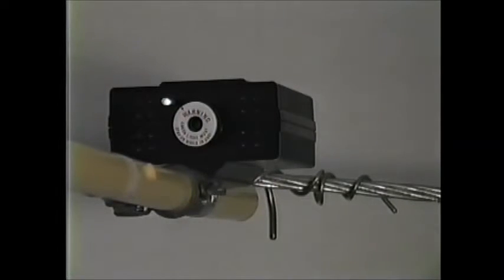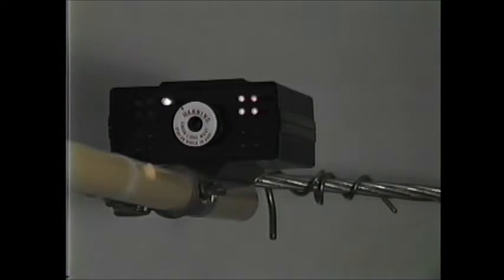Next, we will take the voltage up between 2,000 and 7,000 volts. This will activate the first two banks of lights. Again, this would be the indication you would get for a 4,800 volt system or a 7,200 volt system if you had full system voltage. Again, if you were testing a 12 kV, 25 kV, or a 35 kV system, you know you have more than 2,000 volts but certainly less than system voltage.